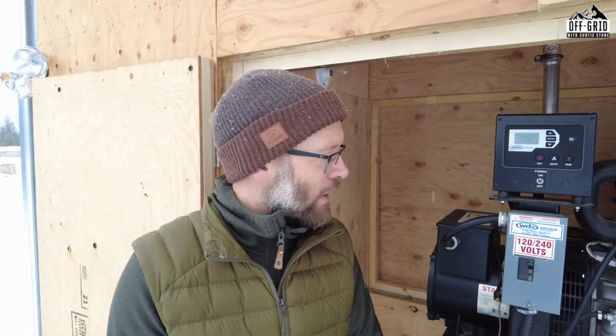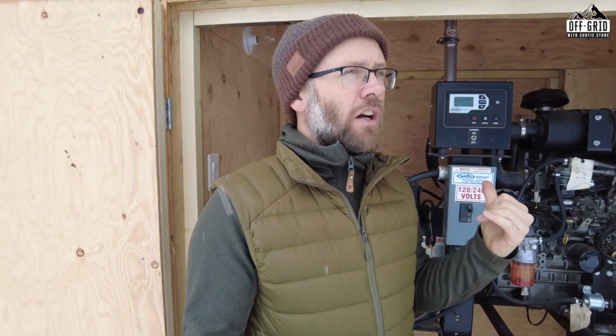So what happens with this generator is when it gets triggered, it'll fire up and start warming up. It has a 3-minute warm-up cycle, and then it'll load. And what happens then is that load goes towards the batteries and the load. So whatever's being consumed, it'll go towards the batteries, and I can set it. In my Schneider system, I can set the battery charge rate. By default, I have it about 50%. When this kicks on, I find it's most efficient to let this produce about 80%, somewhere between 10 to 11 kilowatts instead of maxing it at 13 kilowatts.